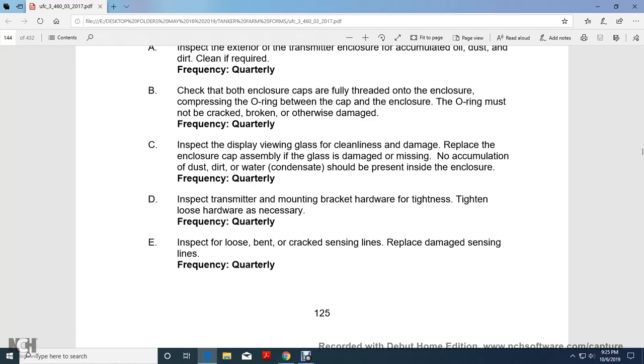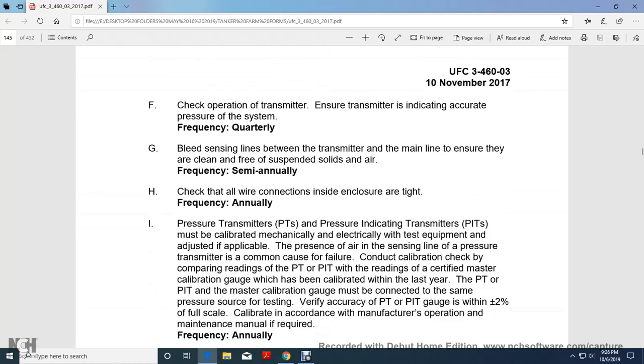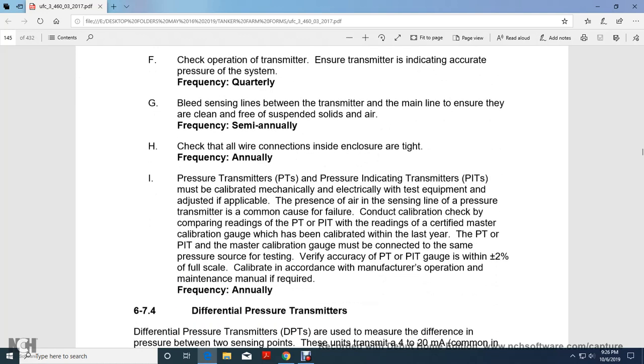Quarterly, inspect for loose, bent, or cracked sensing lines. Replace damaged sensing lines. Quarterly, check the operation of the transmitter. Ensure the transmitter indicates the accurate pressure for the system. Bleed the sensing lines between the transmitter and the main line. Ensure they are clean and free of suspended solids and air, semi-annually. Check the wire connections and ensure the enclosure is tight.